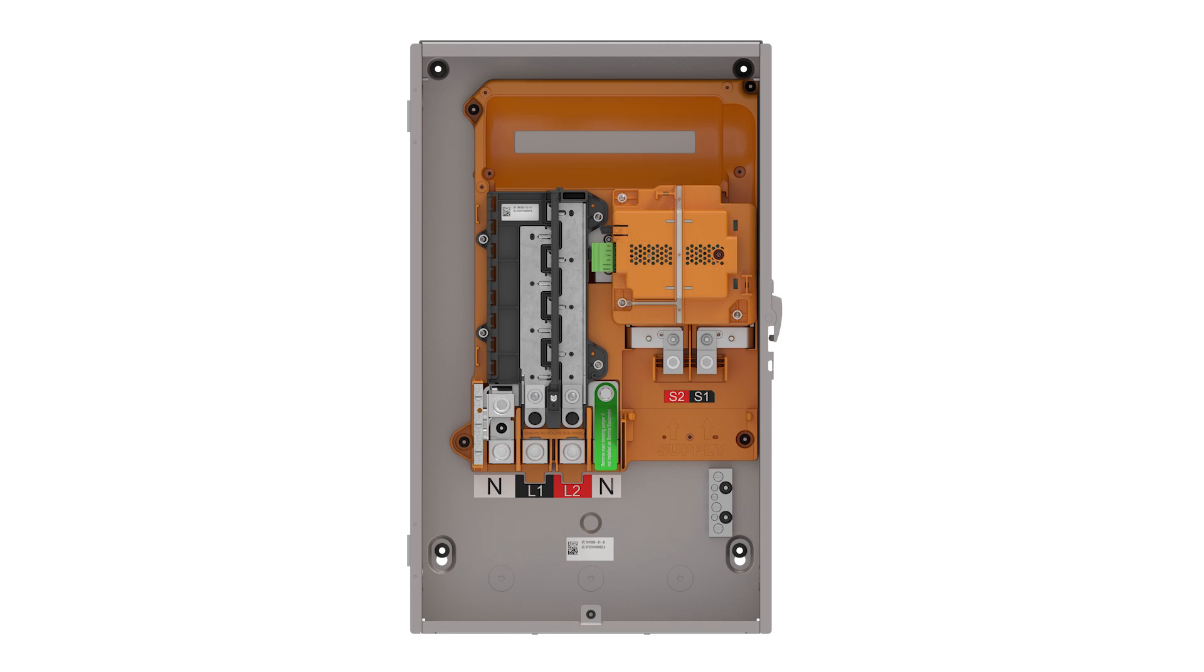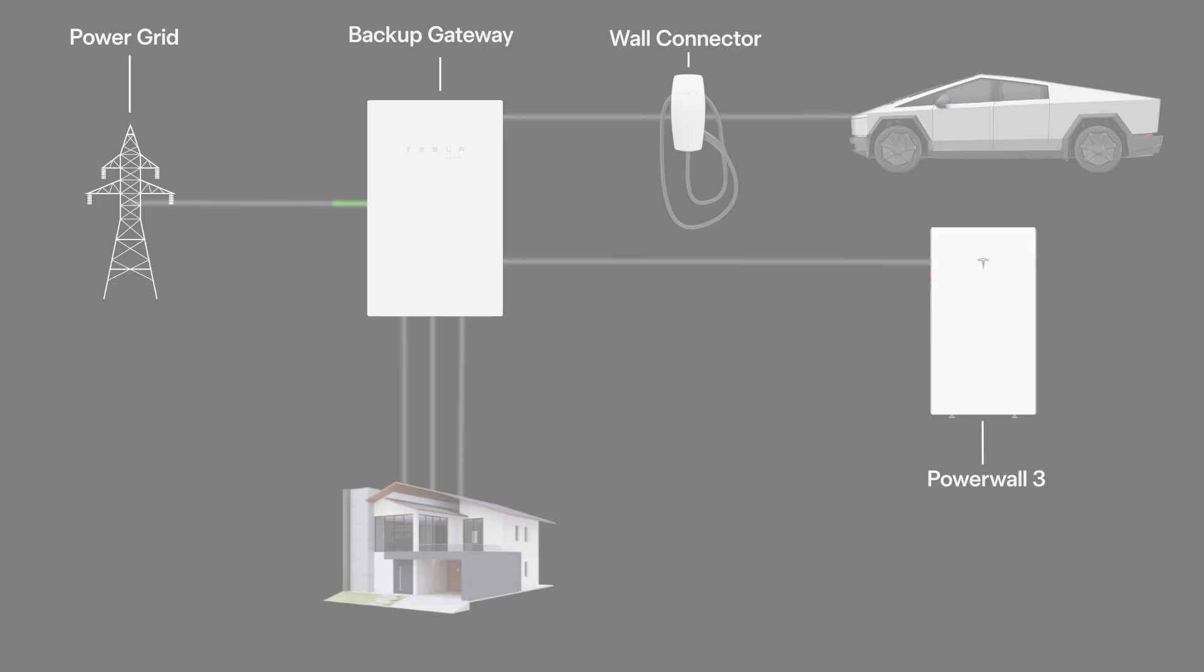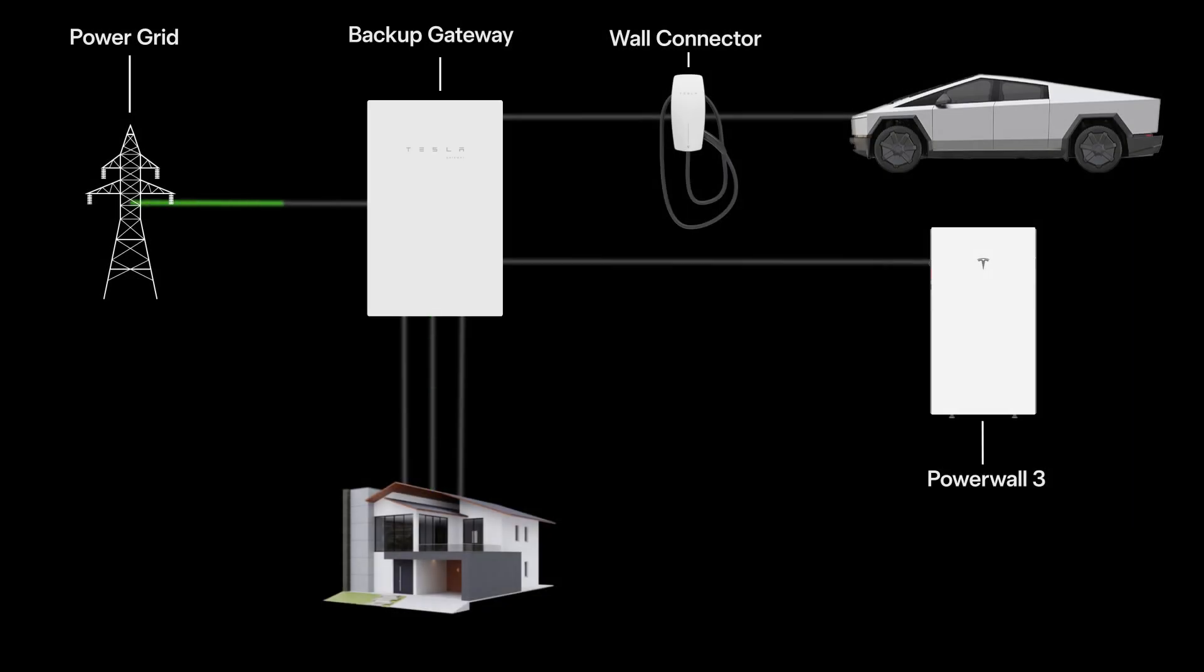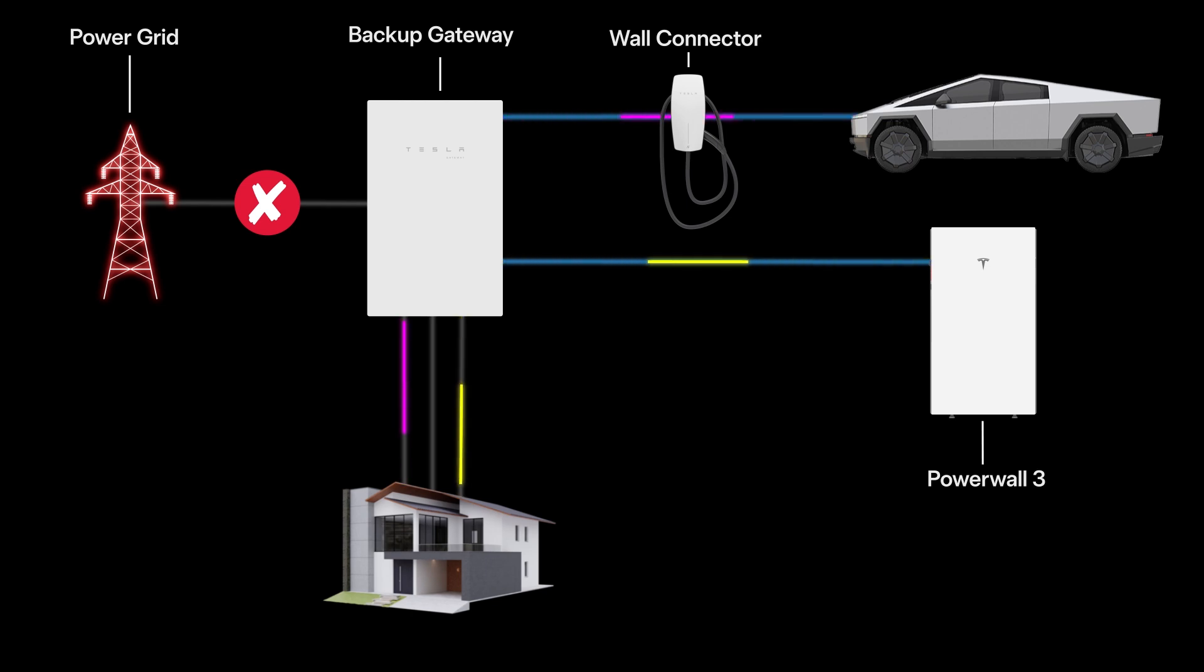In the event of a grid outage, Gateway opens its contactor, electrically isolating the home from the utility grid. At the same time, Gateway signals Powerwall or a PowerShare-compatible vehicle to begin discharging to the home, forming a microgrid.